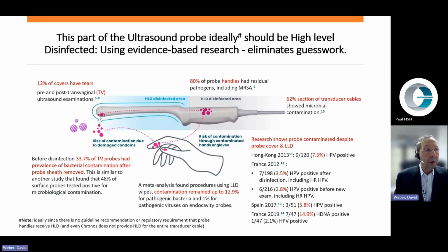Okay, let's turn now to the part of the probe that should ideally be high-level disinfected using evidence-based research, which eliminates guesswork. So here's some of the data based on what I've already told you. 13% of covers have tears. Pre- and post-transvaginal ultrasound examinations have demonstrated this. Before disinfection, approximately 44% of transvaginal probes had presence of bacterial contamination after the probe sheath was removed. That is, in removing the probe sheath, either the hands of the provider or the outside of the probe comes into contact with the area that needs to be high-level disinfected.